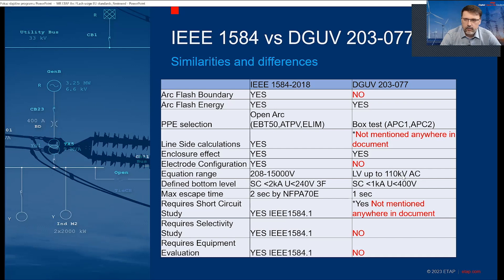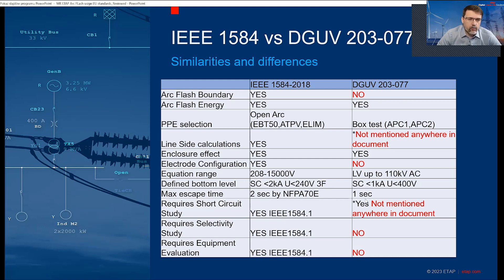Defined bottom level for calculations: IEEE 1584 (latest release) gives 2,000A at 240V three-phase; DGUV has 1,000A at 400V — but again, no background given. Maximum escape time: as per NFPA that's two seconds — not a limit for calculations, but more like escape time for a person under an arc flash event. And DGUV states one second, which we'll stick to for the calculation later.